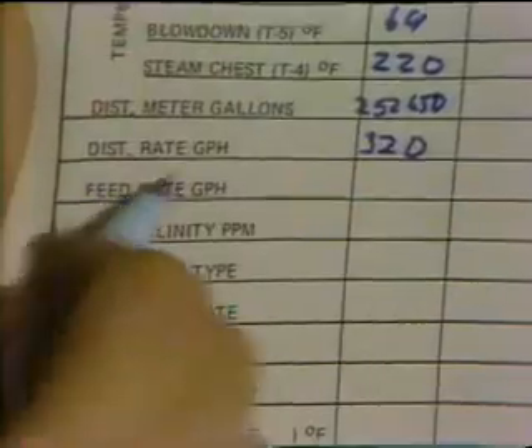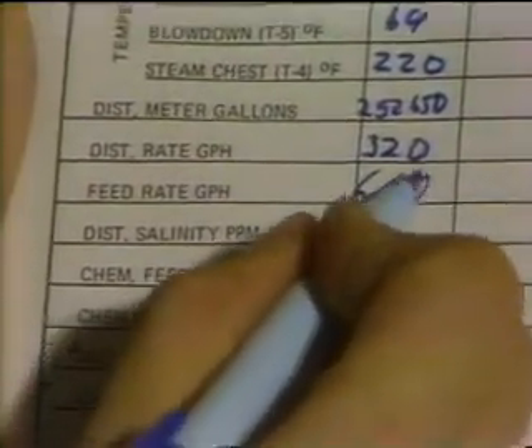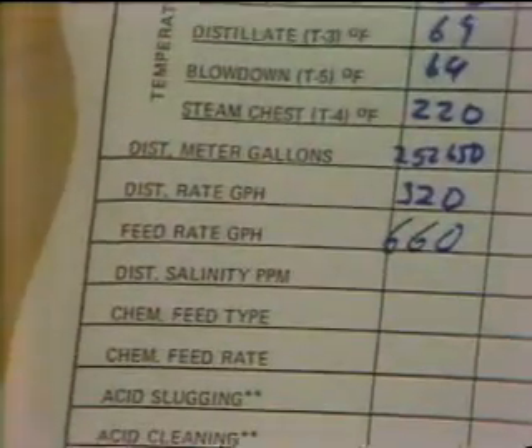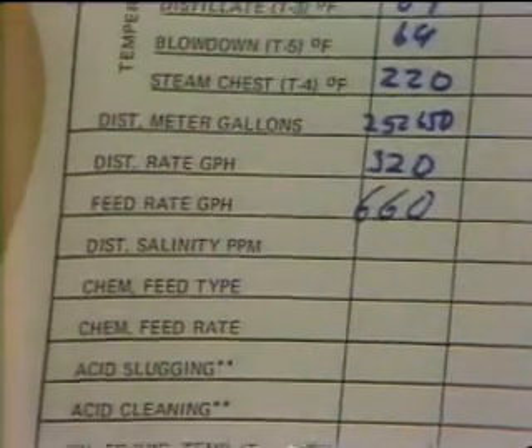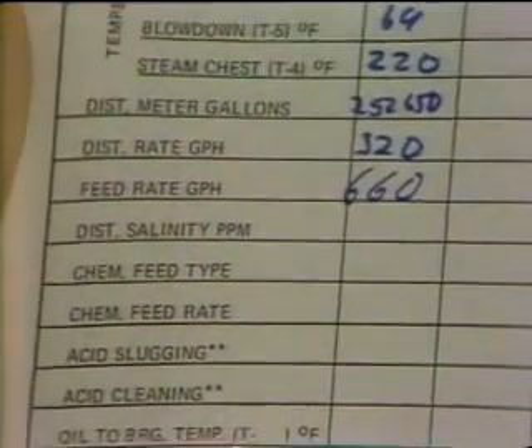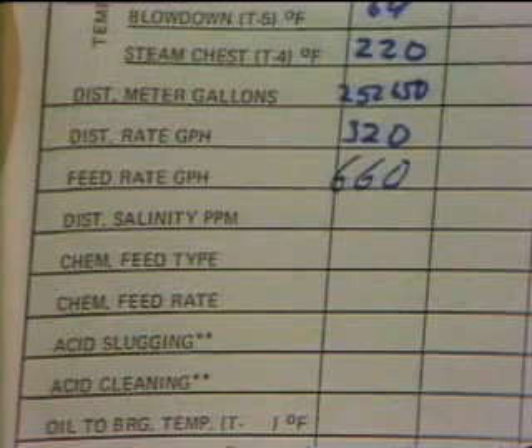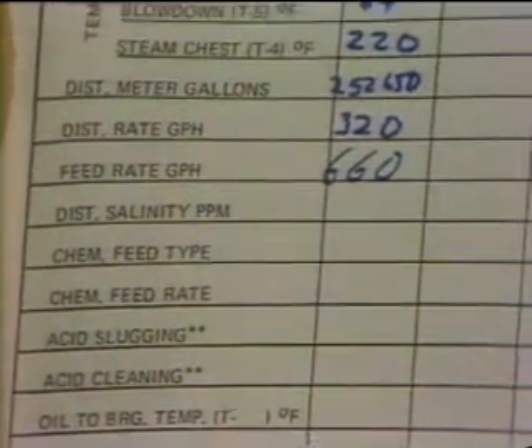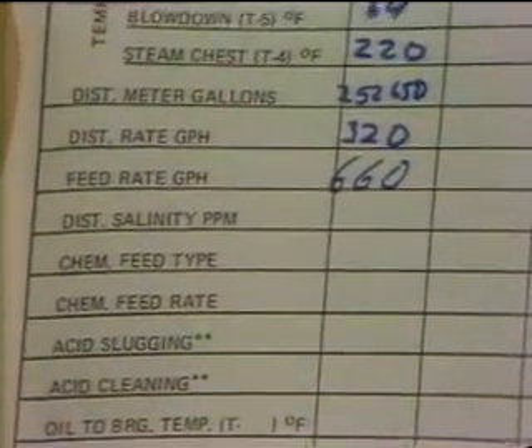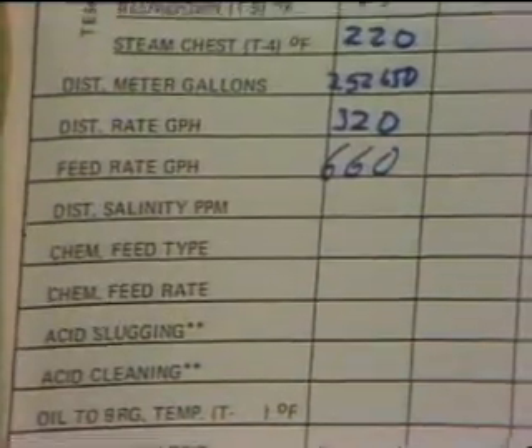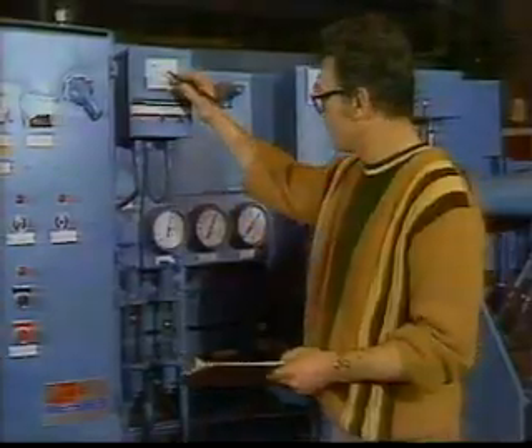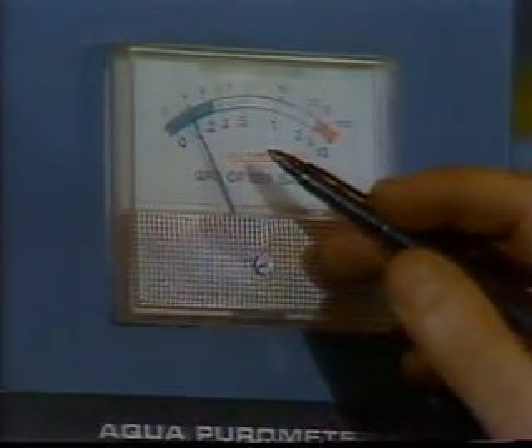Feed water flow rate is logged. It should be about double the distillate reading. This is very important because if the feed water flow is less than that, the concentration of seawater in the boiling chamber of the evaporator will increase and cause a calcium sulfate scale. This leads to a treatment program using AC8. The salinity meter reading is taken next.